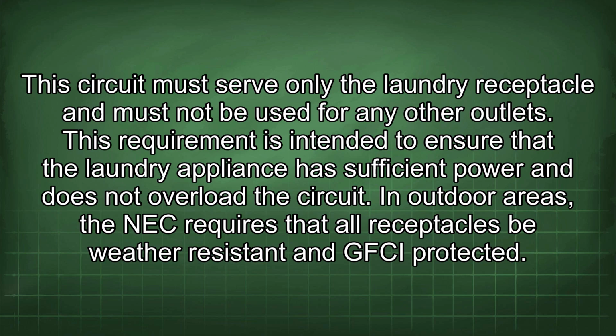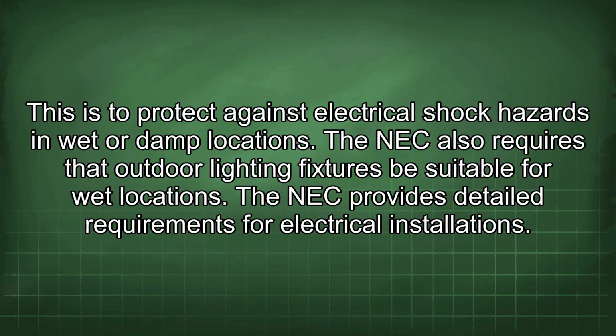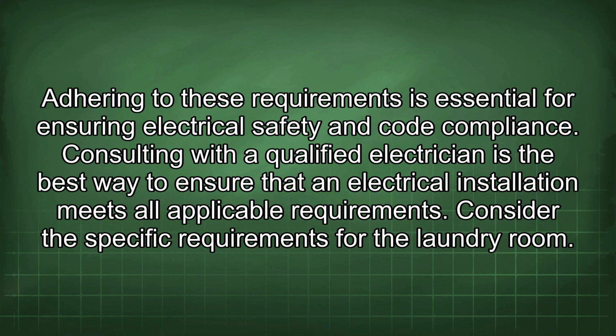In outdoor areas, the NEC requires that all receptacles be weather resistant and GFCI protected. This is to protect against electrical shock hazards in wet or damp locations. The NEC also requires that outdoor lighting fixtures be suitable for wet locations. The NEC provides detailed requirements for electrical installations. Adhering to these requirements is essential for ensuring electrical safety and code compliance. Consulting with a qualified electrician is the best way to ensure that an electrical installation meets all applicable requirements.